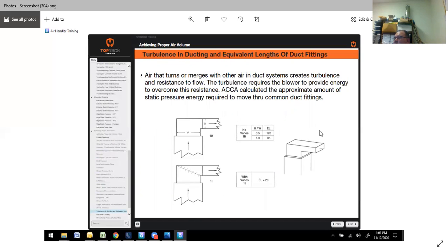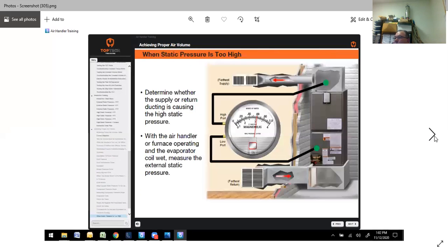Now, this is a kind of a poor example here. This would be a perfect application for a horribly high duct system. Horribly high static, right out of the cabinet. You're going up 10 inches and turning hard. That's going to create excessively high static pressure.